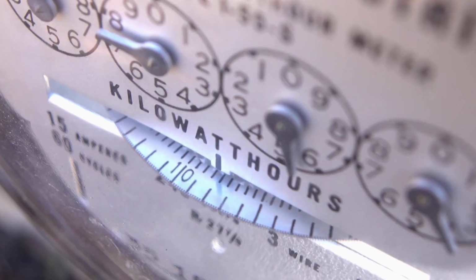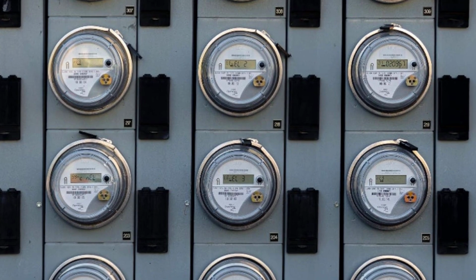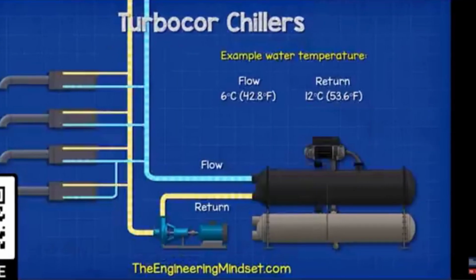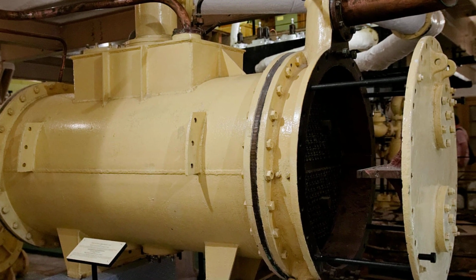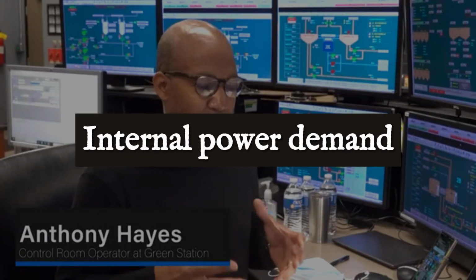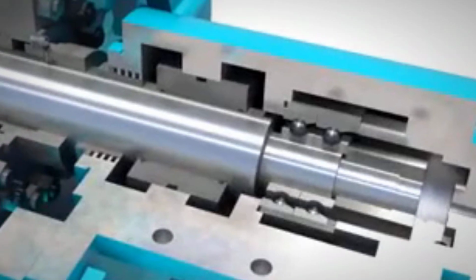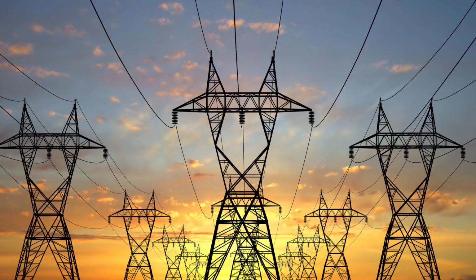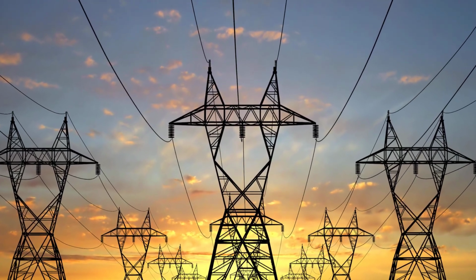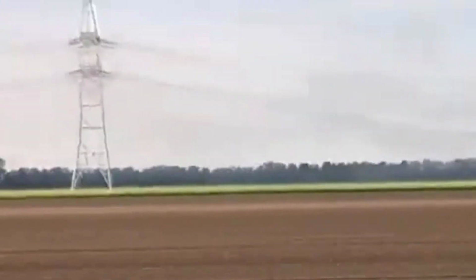Thirdly, this approach would squander a considerable amount of energy. It is generally more economical to cool the steam just enough to condense it back into liquid water for reuse as feed water. But even this presents an enormous challenge. As discussed in a previous video, power plants do consume a considerable amount of energy for their internal processes, including cooling. While the net output is positive, any energy diverted for these operations is energy not delivered to the grid, highlighting the need for highly efficient cooling.